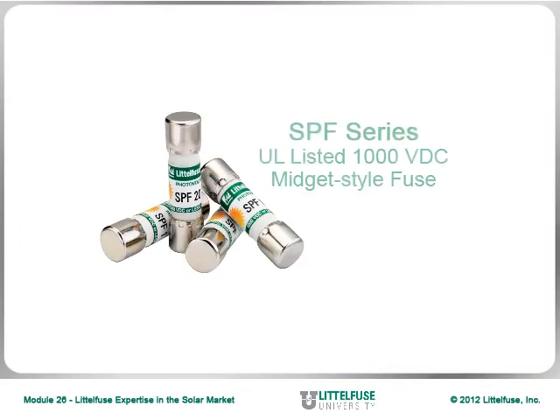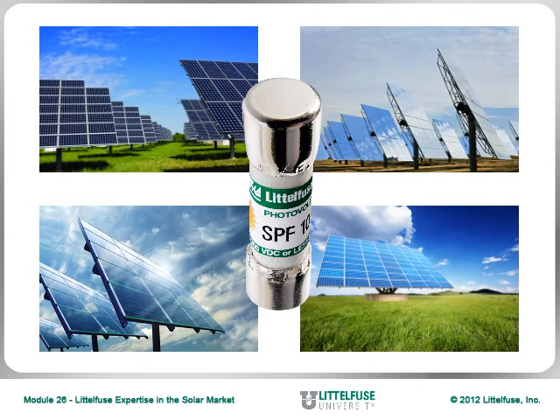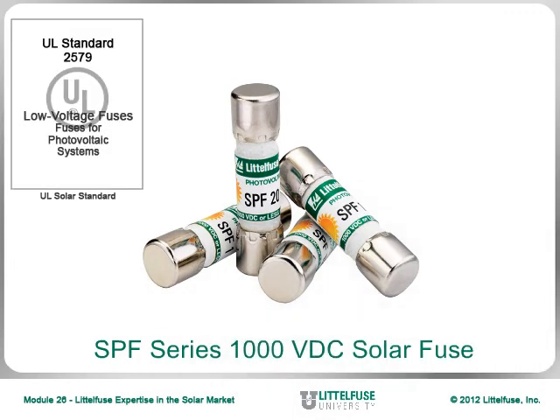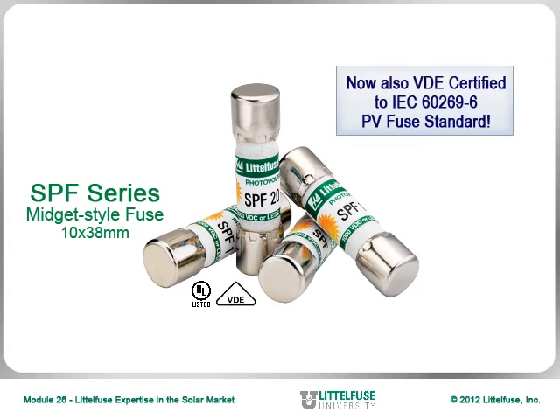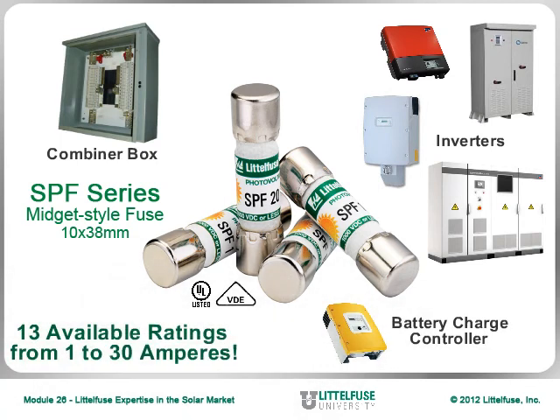To finish up this module, let's briefly review the second of the solar-related fuses featured here: the SPF midget-style solar fuse. The 1000V DC-rated SPF series of solar fuses have protected thousands of strings in photovoltaic or PV systems. As voltage needs have increased, so have the corresponding standards. The SPF series now meets both UL2579 and IEC 60269-6 requirements for higher system voltages, low overload interruption, and unique environmental conditions. The SPF SolarFuse is a UL-listed midget-style fuse designed for photovoltaic applications such as combiner boxes, inverters, and battery charge controllers, and is available in an industry-leading 13 amperage ratings ranging from 1 to 30 amperes.